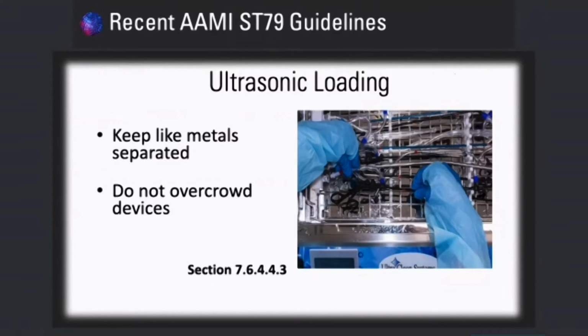Keep like metals separated. There's actually a kind of bonding or welding that can occur between unlike items. So it's really good to avoid creating this galvanic effect in your basin, where metals are leaching out and touching each other, causing pitting against each other. So not a good thing. And of course, don't overcrowd your instruments. Try to make sure you have enough throughput for the instruments or the machines that you acquire.